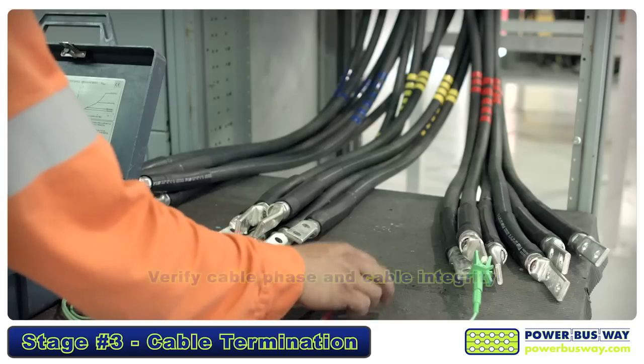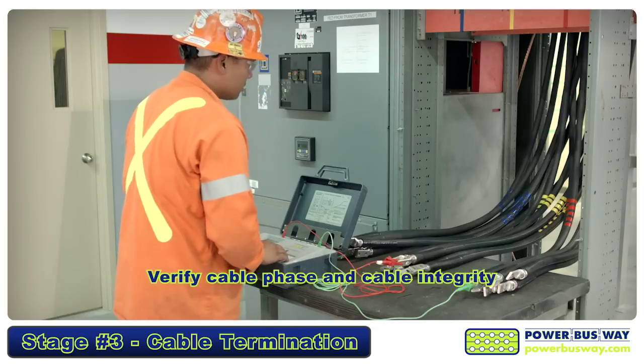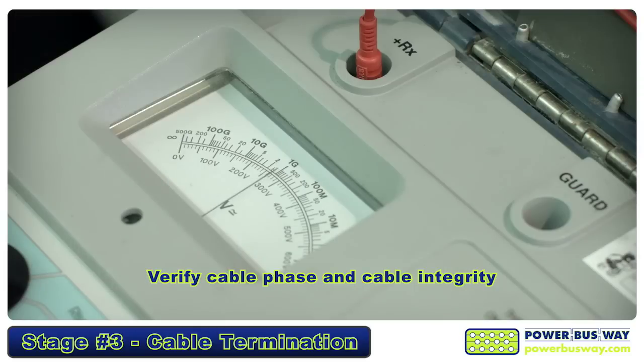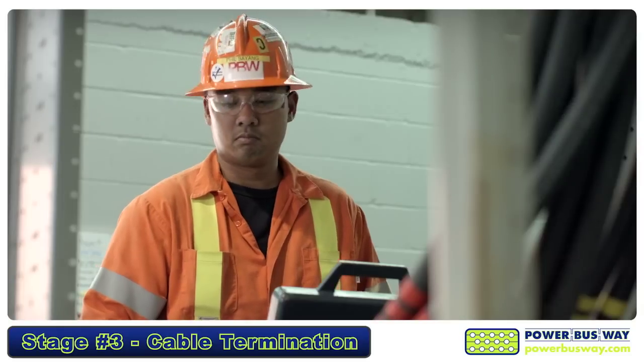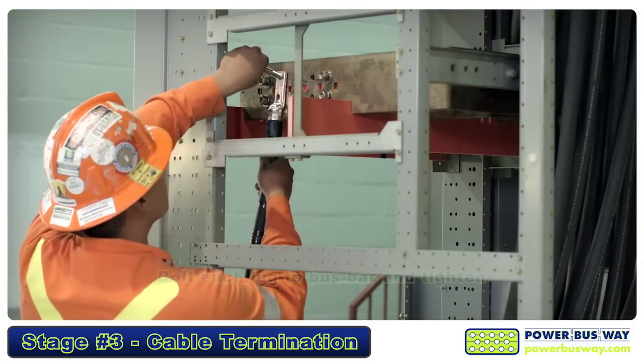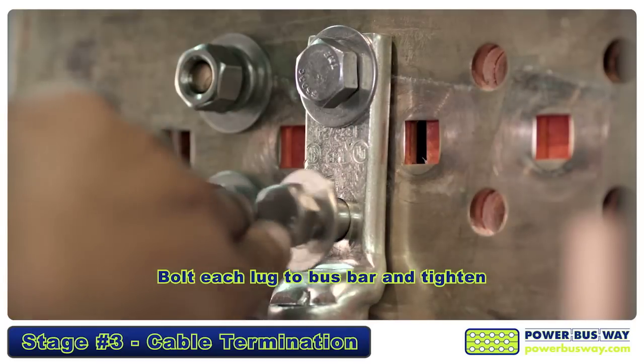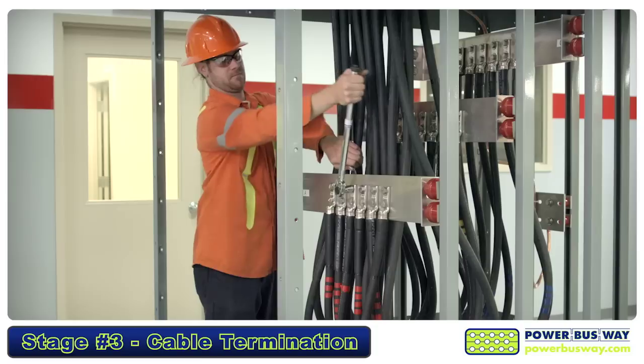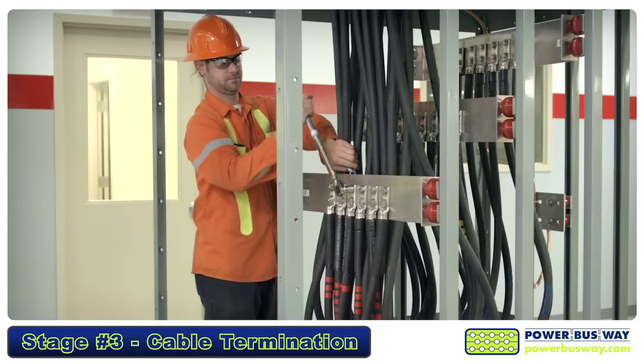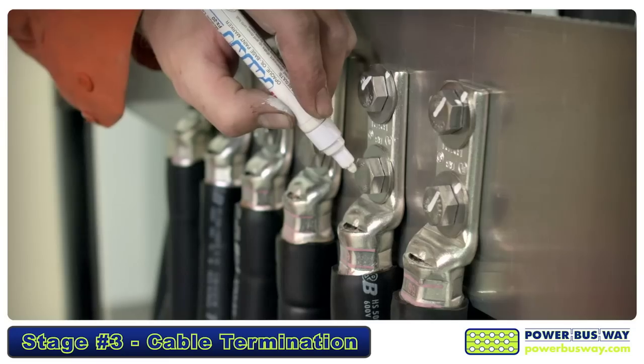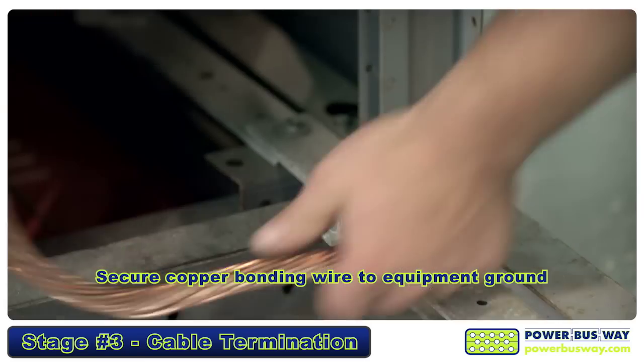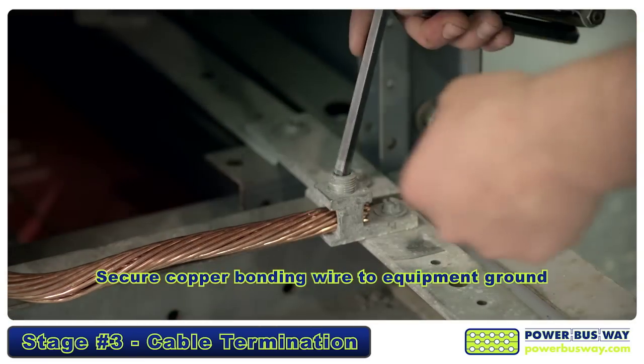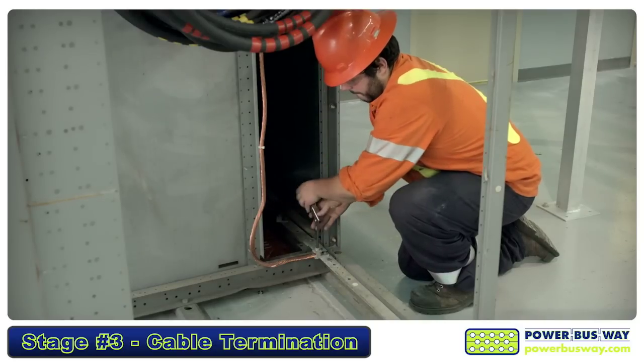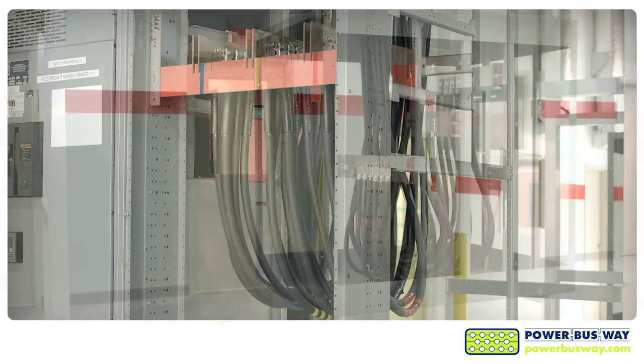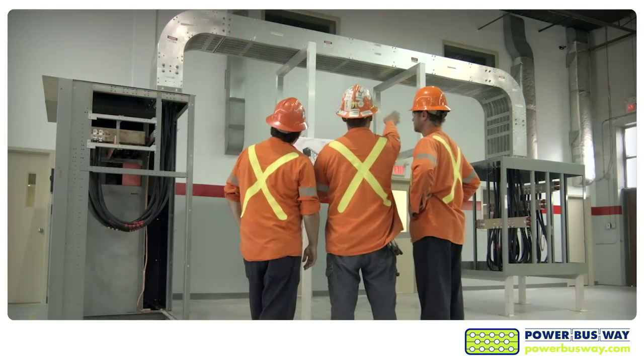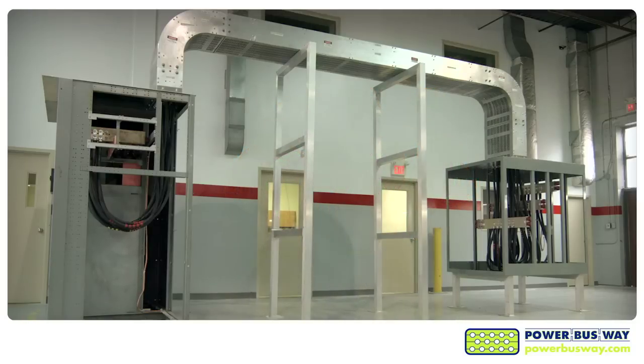After the cables have been sealed, it's imperative to test each cable to verify that the phase identification is correct and that the cable insulation has at no point been compromised. Satisfied with the integrity of the cables, you may now bolt each lug to the bus bar and tighten with the appropriate hardware. Using a torque wrench, torque each bolt to the specified rating. Finally, secure the copper bonding wire to the equipment ground. Once each termination compartment has been verified and closed up, your cable bus installation is ready to be energized.